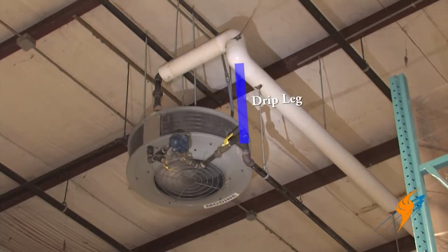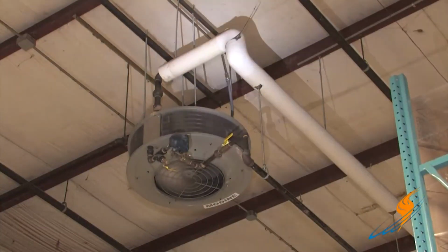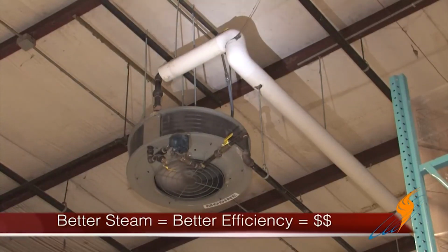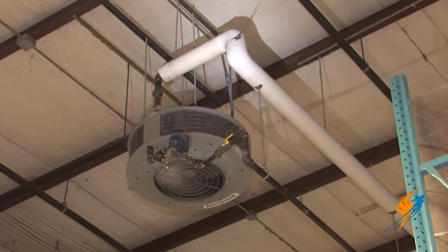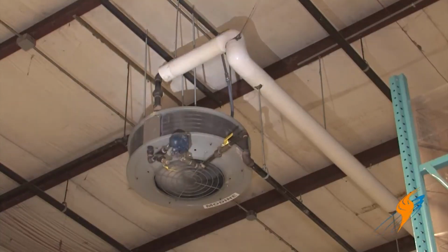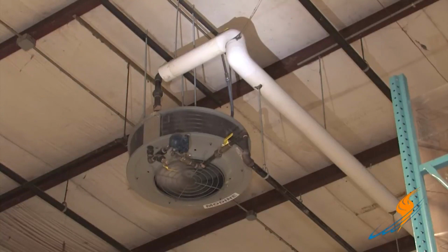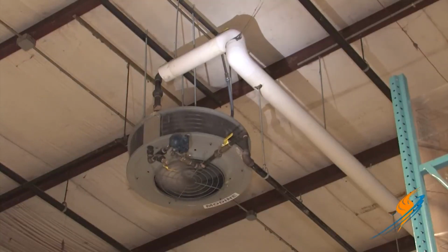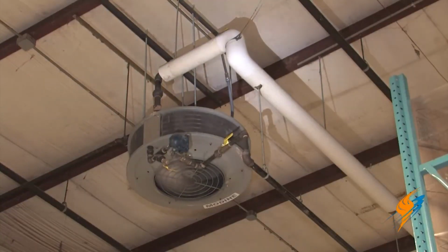And what that will do is that'll prevent water from accumulating in this horizontal line, and also it'll provide better steam for this unit. If all of the condensate generated in the piping goes through this unit, it's not going to put out 20% of the heat that the previous unit will. So that's a frequent oversight, and we just need to make sure that we have an end of main trap.